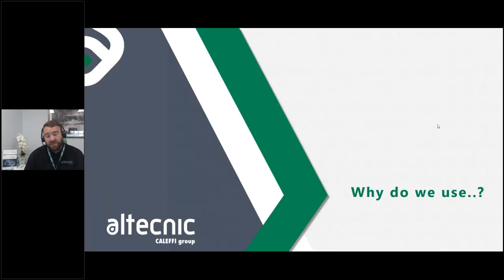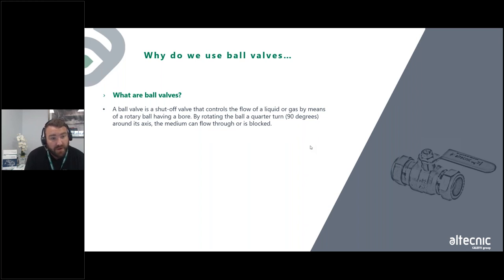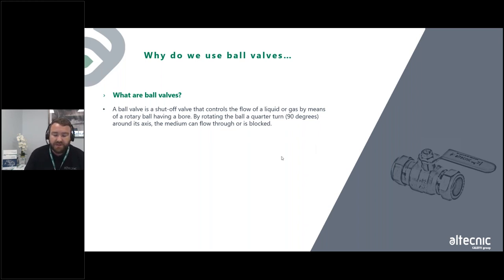The first thing to address is: why do we use ball valves and what's their intended use? A ball valve is a shut-off valve that controls the flow of a liquid or a gas by means of a rotary ball. By rotating the ball a quarter turn, or 90 degrees, around its axis, the medium can flow through or can be blocked — so we use it as isolation. That's their intended use.